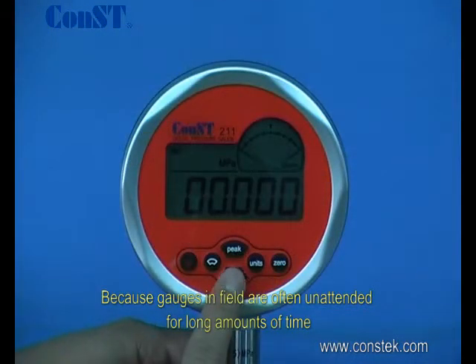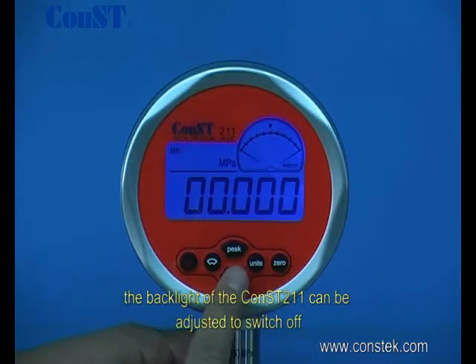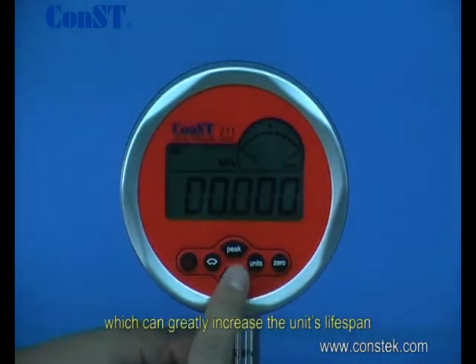Because gauges in the field are often unattended for long amounts of time, the backlight of the ConST211 can be adjusted to switch off in time increments of 10, 20, or 30 seconds, which can greatly increase the unit's lifespan.